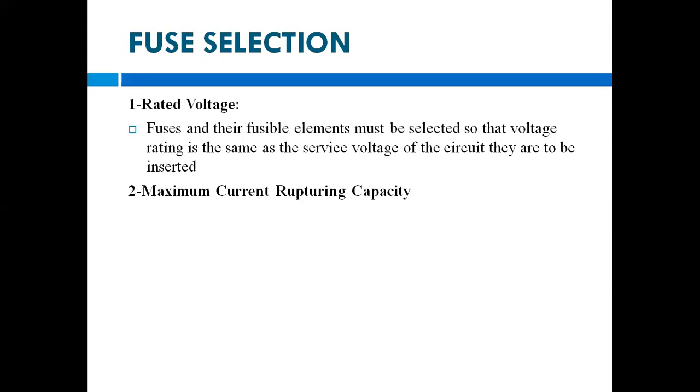The fuses and their fusible elements must be selected so that the voltage rating is the same as the service voltage of the circuit. That means whatever the normal circuit voltage is, at minimum that voltage should be borne by that fuse.